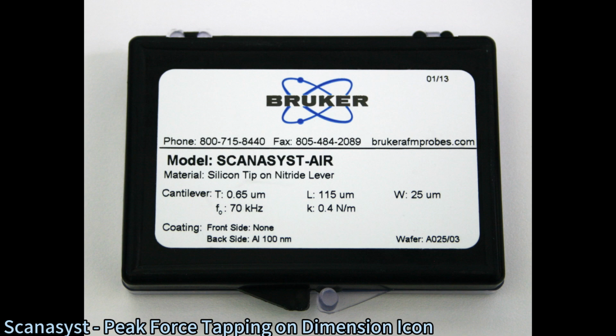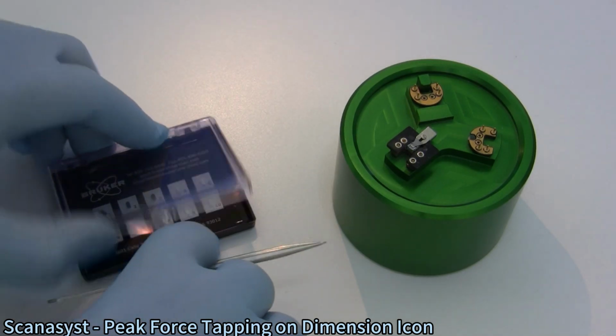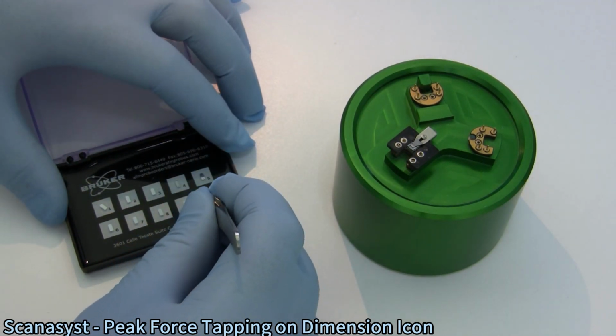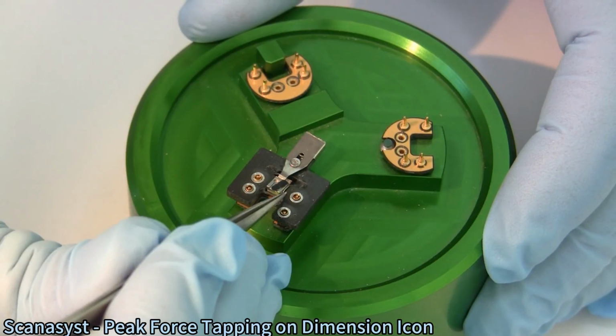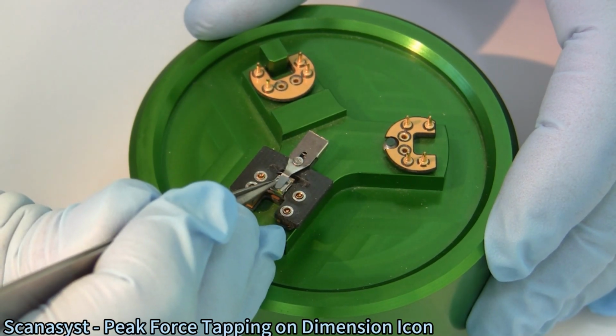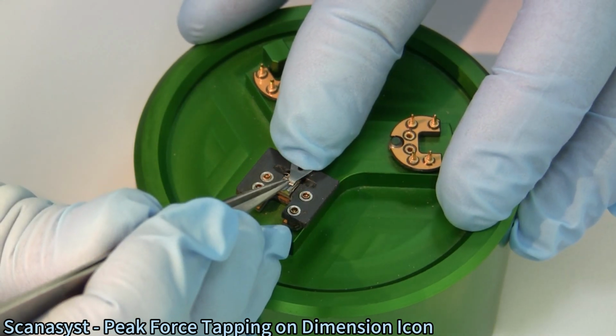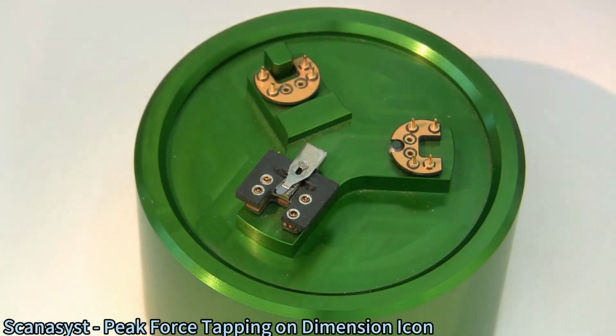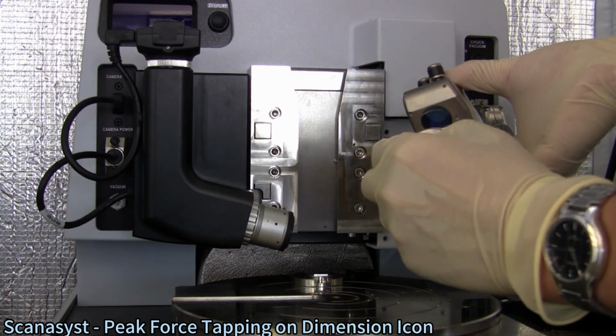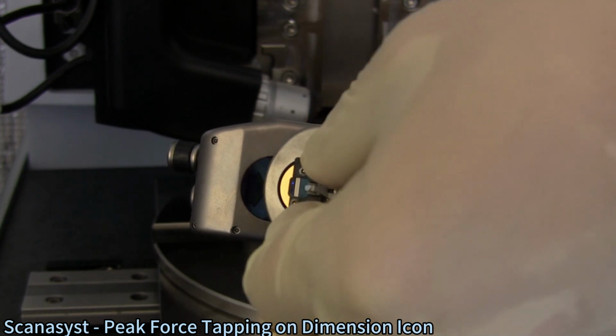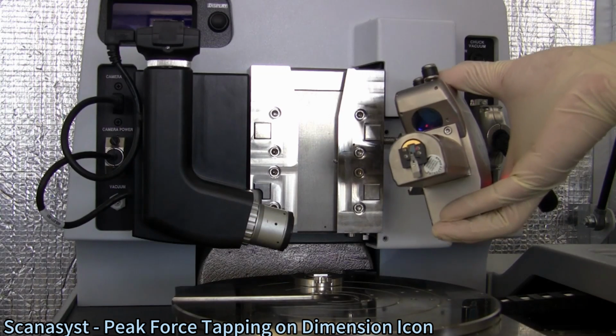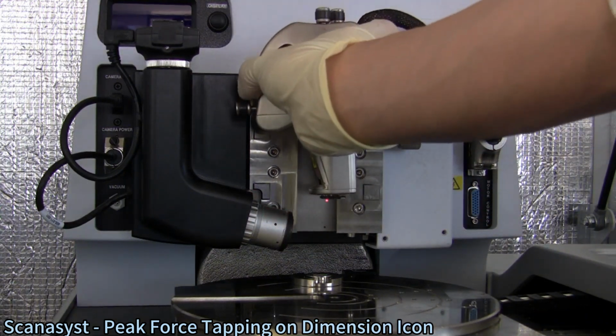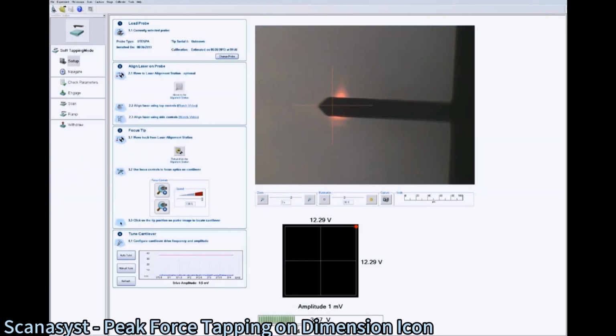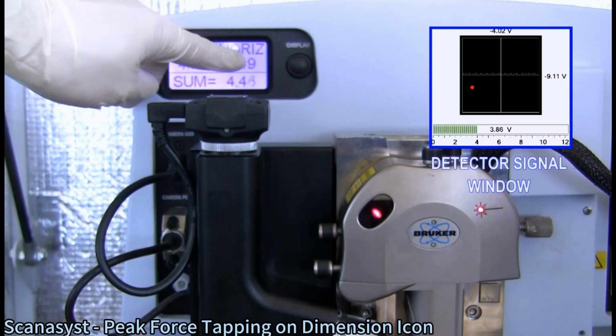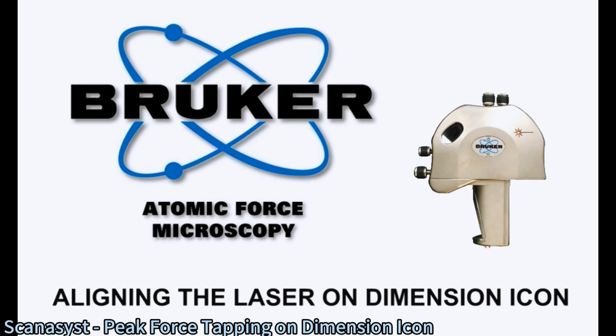ScanAsyst probes have relatively low force constant cantilevers that are suitable for low force loads and low frequency cycling. Insert a probe into the specialized holder using a pair of tweezers and the probe mounting tool that comes with the system. Fix the probe into place using the spring clip. Place the probe carrier onto the scanner and return the scanner to the dovetail cradle. The process of using the shadow method to position the laser onto the cantilever and aligning the photodetector is described in great detail in the probe alignment procedure video.